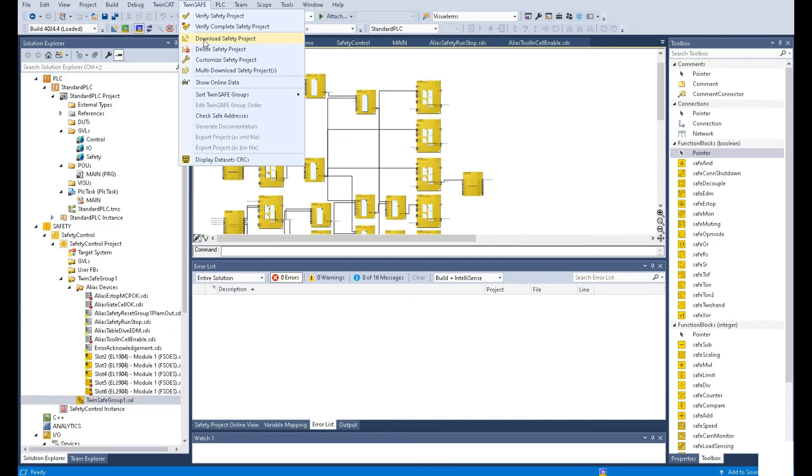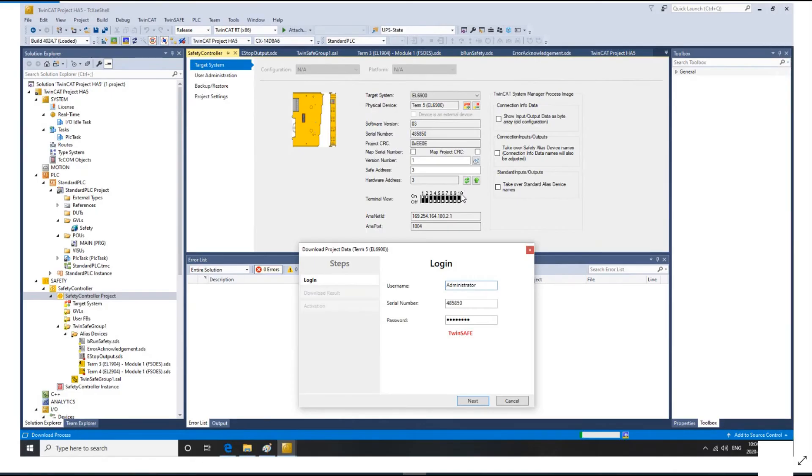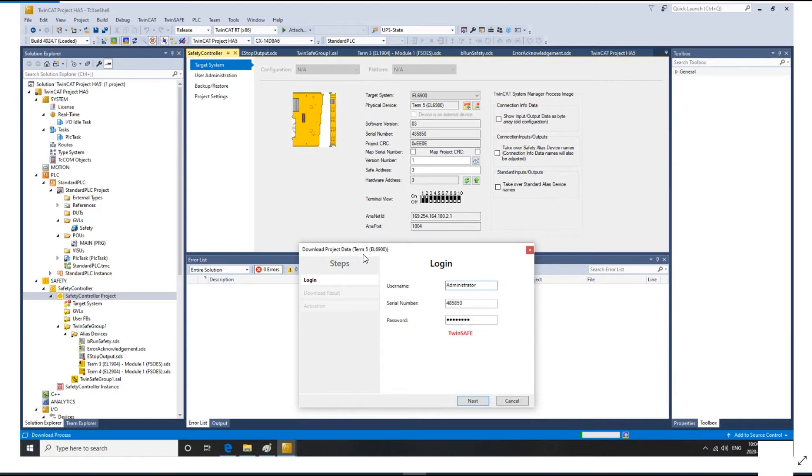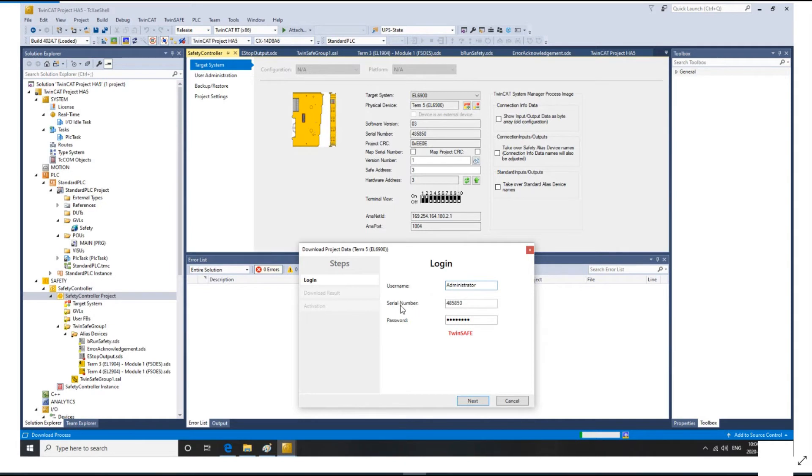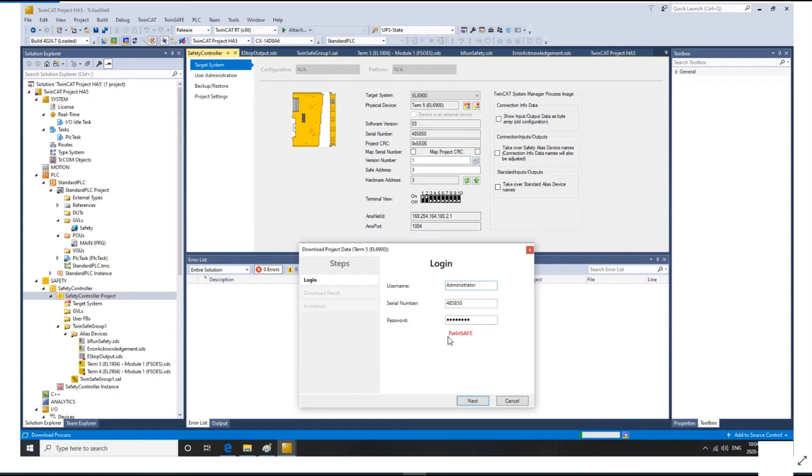Download project data. It will show where your controller is. The username by default is administrator. And the series number, you need to copy this series number and paste it here. The password by default is TwinSafe. Keep in mind, TwinSAFE is capital. And click next.